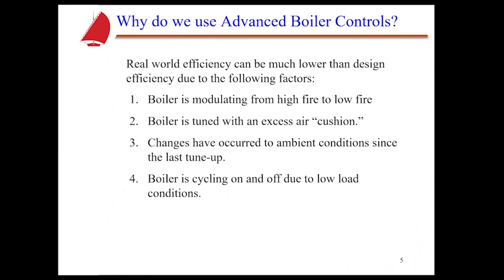In real world efficiency, it can be a lot lower than the designed efficiency, and it can be due to the following factors. Boilers are usually modulating from high fire to low fire continuously. And there's very few boilers out there that just set at high fire throughout the day or throughout a production period. And so therefore, when we're modulating, we need to make sure, if we possibly can, that we're at the optimum air-fuel ratio point, regardless of where we're at in that firing rate range. And the boiler is tuned with an excess air cushion with a linkage type system so that we don't go into a rich condition, which can be dangerous. So there's always that excess air actually dialed in to the air-fuel ratio with a linkage type system.